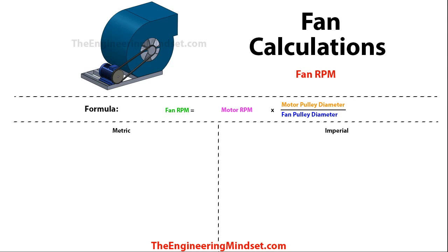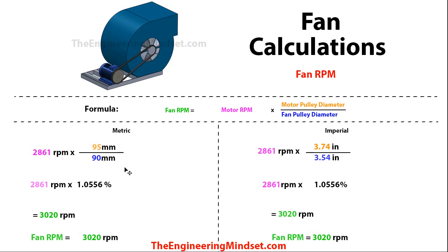We can also calculate the fan RPM needed to achieve our design criteria. The formula is: fan RPM = motor RPM × (motor pulley diameter ÷ fan pulley diameter). We already know these figures from the manufacturer or design data. Doing the division of the pulley diameters gives a ratio, and multiplying out brings us to 3020 RPM — the speed the fan needs to rotate at to achieve the design flow rate.